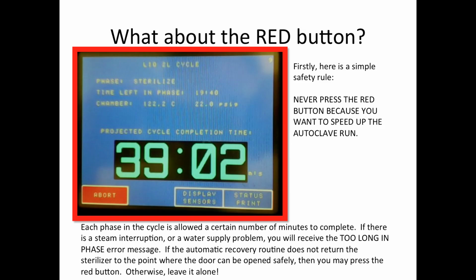There are times when you may need to use the button, though. Each phase in the cycle is allowed a certain number of minutes to complete. Now, if there is a steam interruption, a water supply interruption, you may receive what's called a too long in phase error message. If the automatic recovery routine does not return the sterilizer to the point where the door can be opened safely, then you may press the red button.